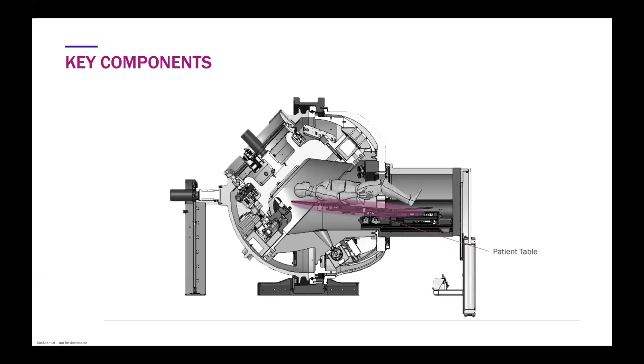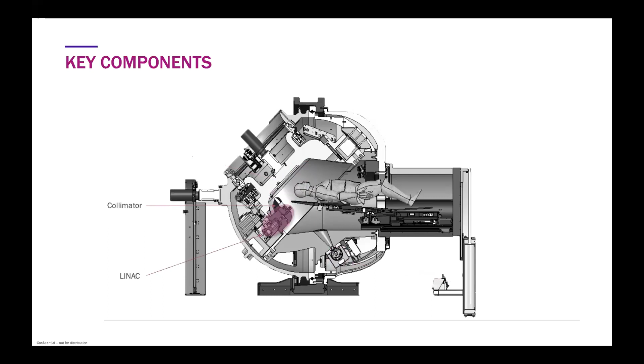The targeting device uses something like the CyberKnife. It uses a KV tube and a KV amorphous silicon camera, and takes these projection images and correlates them against the DRRs using standard techniques that were devised originally for the CyberKnife. But in this case, we're using a single imager and a single KV source. Finally, we have a collimation system that's best in class, which I'll be showing you a little bit more, that leads to minimal leakage off this primary target and gives you minimal penumbra.